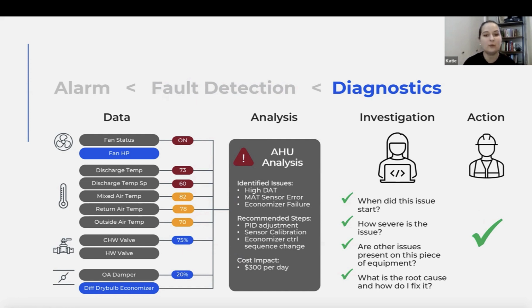So it takes all of this information. It says, I know I have these 3 problems. These are the recommended steps you should take. Either you need to adjust your PID, you've got to adjust your sensors, or you have to make a change to your economizer control sequence. Those are the 3 top recommended steps. So right there, you have some actions to take right out of the gate. So it really saves a lot of desk time and time in the mechanical room, troubleshooting, and potentially going to get the part and coming back, right?